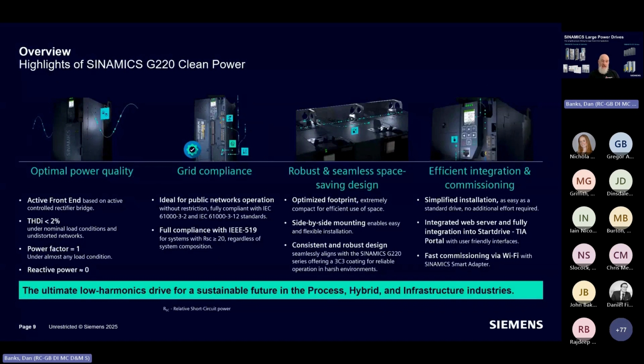So let's hit some of those headline numbers and just really talk about what we're talking about here. THDI in a typical power supply system, lower than 2%. That's a big step up from, I would say, where commonly available clean power or low harmonic drives have previously been. Even our own active front end system, the S120, we would normally say THDI less than 3%. So we're knocking about half the noise out of the system with this new drive. That gives you a power factor of 1 or under almost any load condition with no reactive power at all. So that's really, really neat. Obviously, the drive comes with the compliance with all those IEC and IEEE standards we talked about. But the other thing I'd say that's really important and a big headline for this product for us is size.